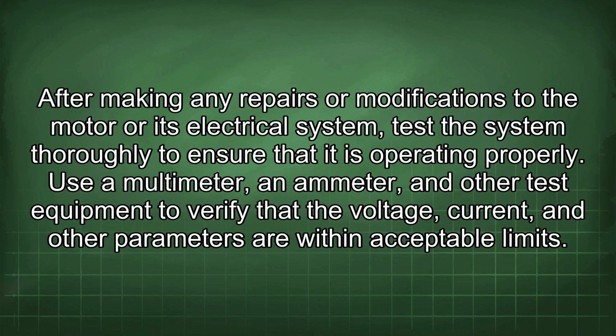After making any repairs or modifications to the motor or its electrical system, test the system thoroughly to ensure that it is operating properly. Use a multimeter, an ammeter, and other test equipment to verify that the voltage, current, and other parameters are within acceptable limits.